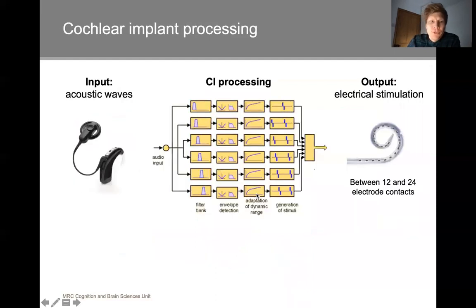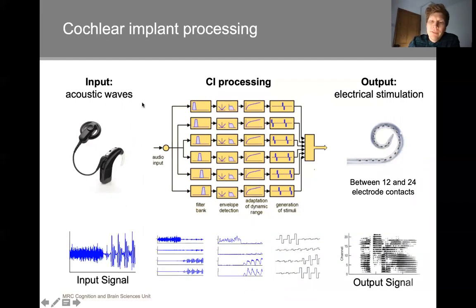In order to do so, the cochlear implant records the input sound. These are the acoustic waves in the environment of the listener via microphones. It then does some signal processing to the signal. It, for example, splits the signal into different frequency bands using a filter bank approach. And that is important because then in each of these different frequency bands, information is extracted from the sound, and that is used to modulate electric pulses.